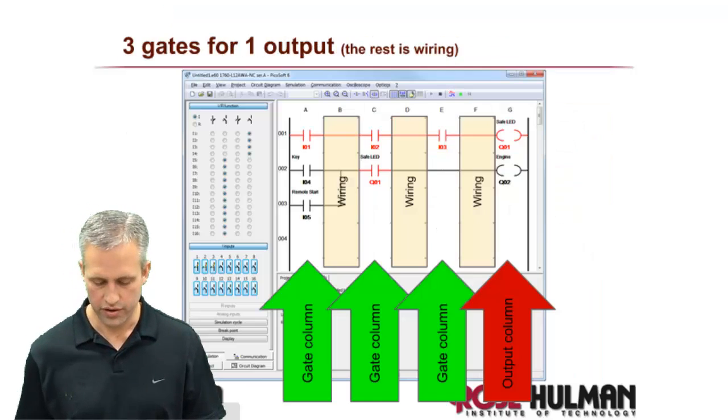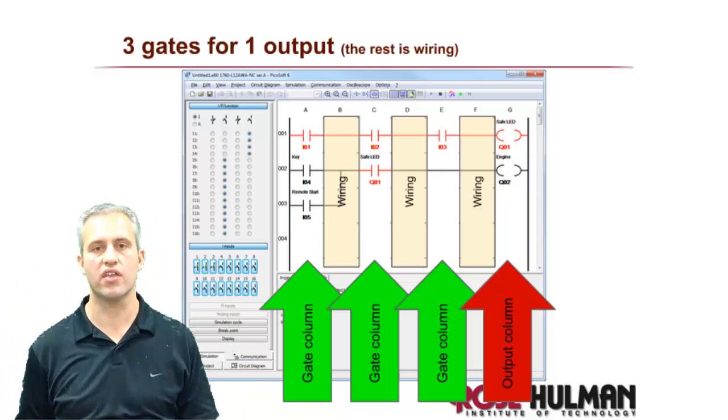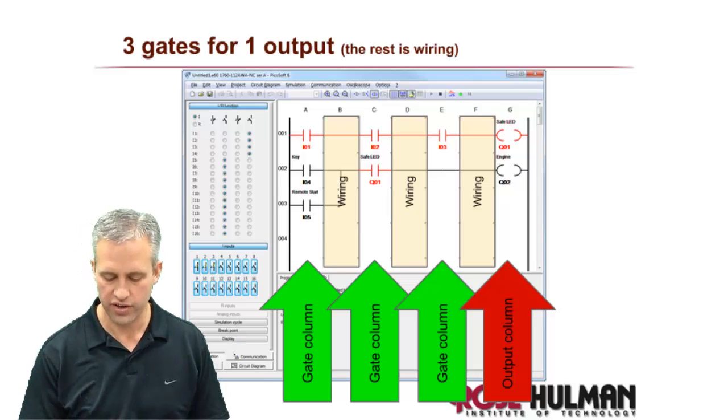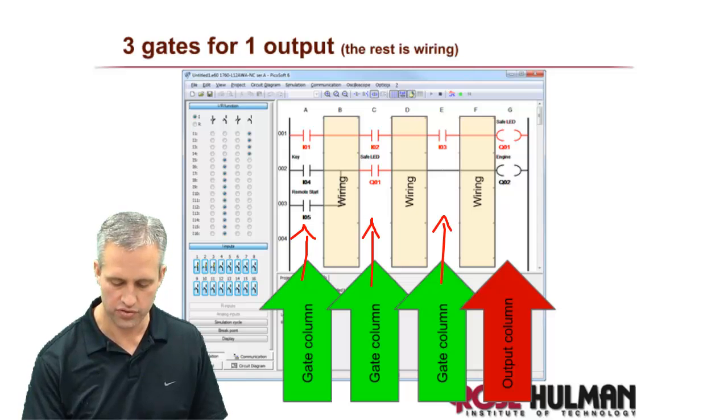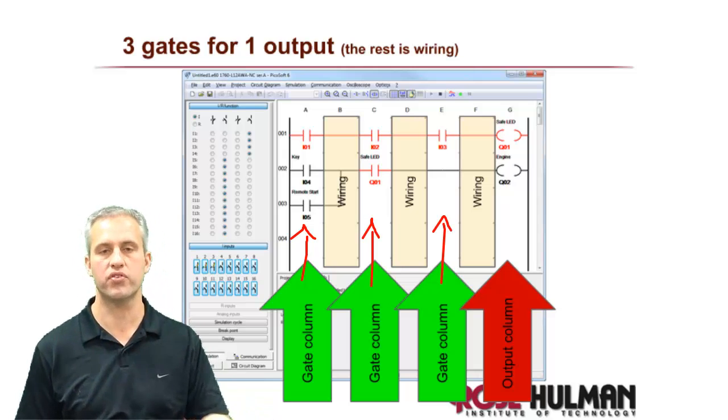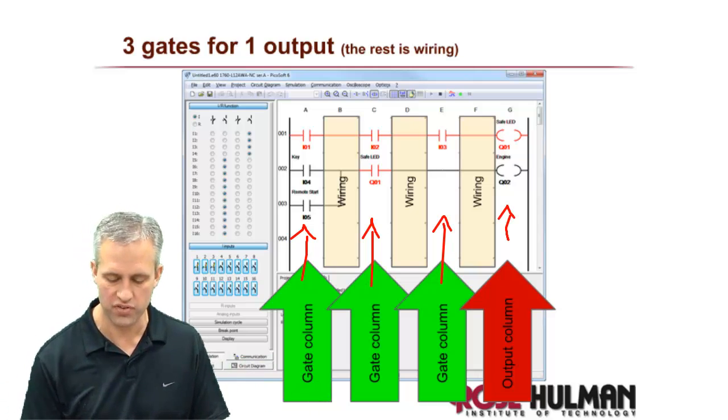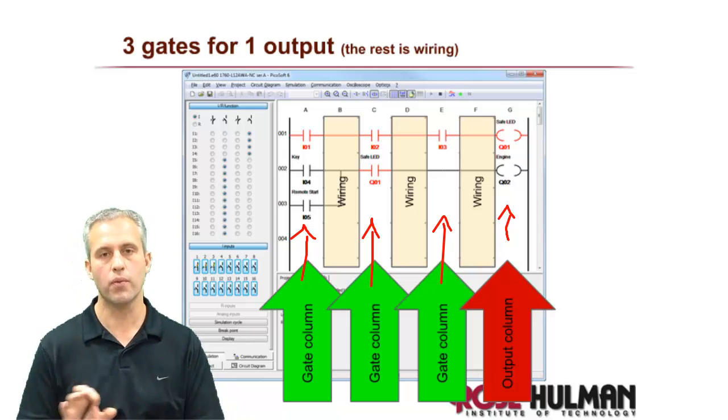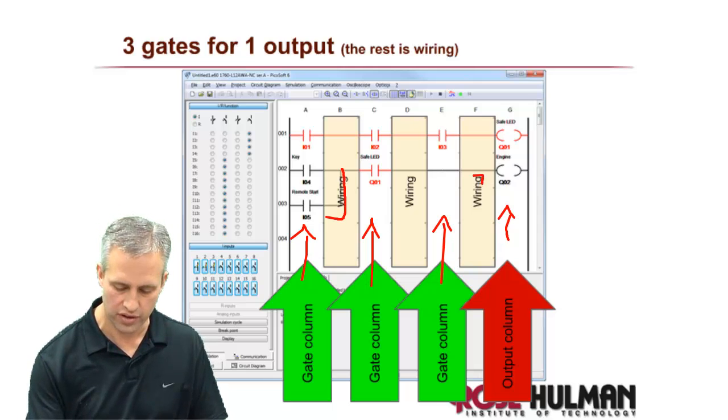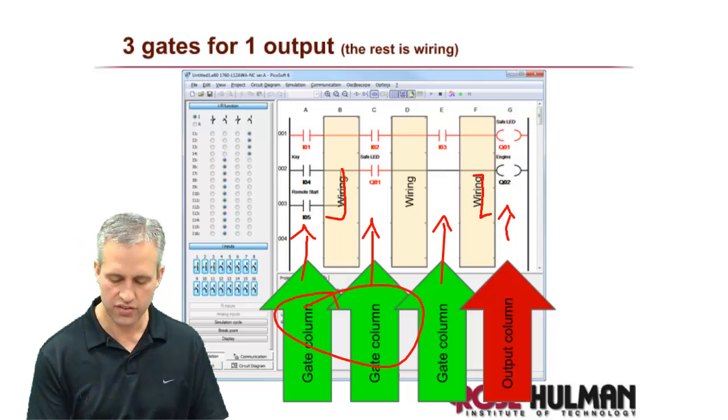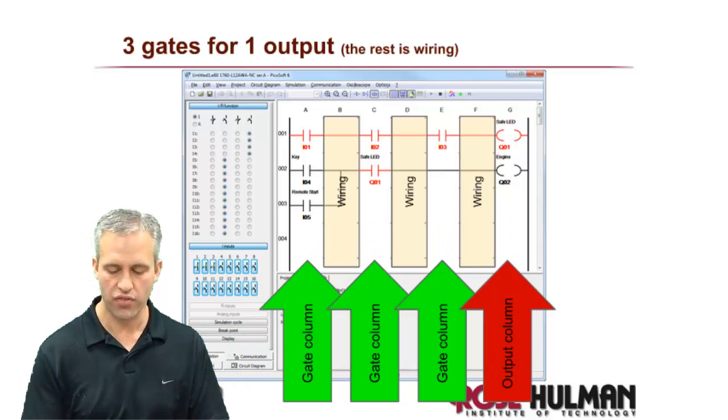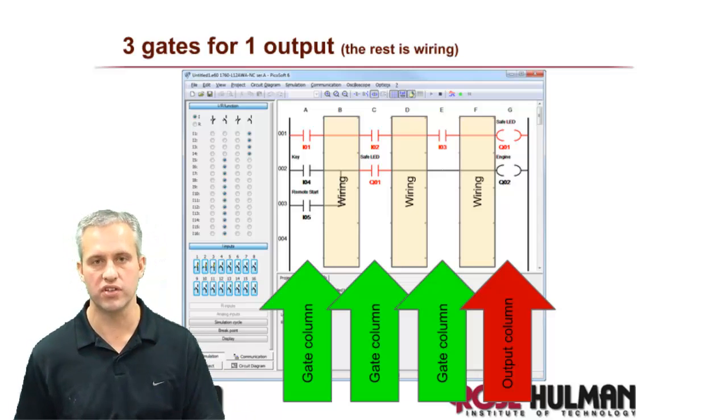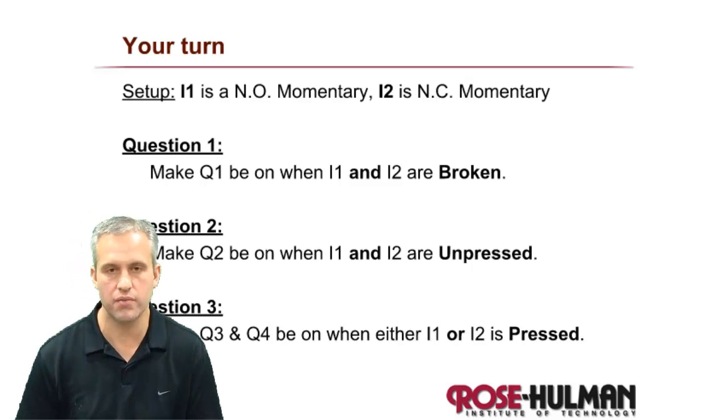Always another slide. The thing I wanted to mention in this slide is that I wanted you to notice how PicoSoft is working. You've actually got three columns that serve as your inputs, so you can put inputs in these three spots. If you want more inputs than that, you have to do some clever thing with multiple rungs. Then this last column is very different—it's an output column. Things will appear differently depending on which column they're in. These three middles are just for wiring, so you can do things like ups and downs. But you get three gates, also called inputs, and one output on each rung. That's how this particular PLC works. Fancier PLCs have more features.